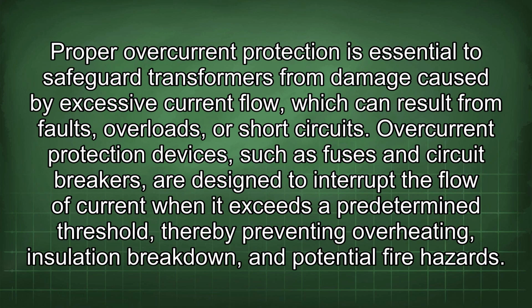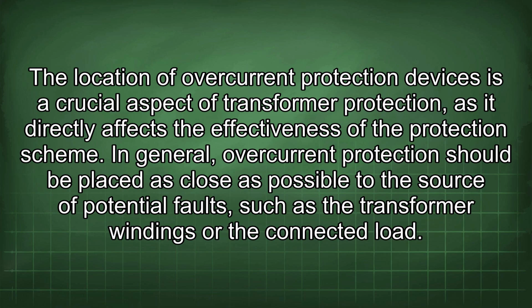Proper overcurrent protection is essential to safeguard transformers from damage caused by excessive current flow, which can result from faults, overloads, or short circuits. Overcurrent protection devices, such as fuses and circuit breakers, are designed to interrupt the flow of current when it exceeds a predetermined threshold, thereby preventing overheating, insulation breakdown, and potential fire hazards. The location of overcurrent protection devices is a crucial aspect of transformer protection, as it directly affects the effectiveness of the protection scheme. In general, overcurrent protection should be placed as close as possible to the source of potential faults, such as the transformer windings or the connected load.